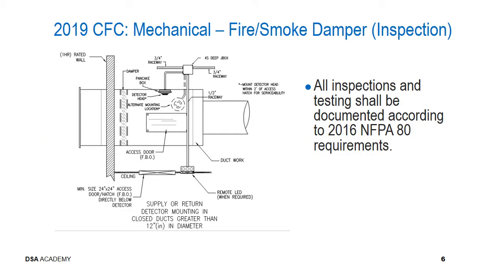Here's a standard detail for a combination fire smoke damper. Note the location of the required access hatch at the bottom, the detector head located within the ductwork, the location of the damper and the rated wall. All inspections and testings shall be documented according to 2016 NFPA 80 requirements.